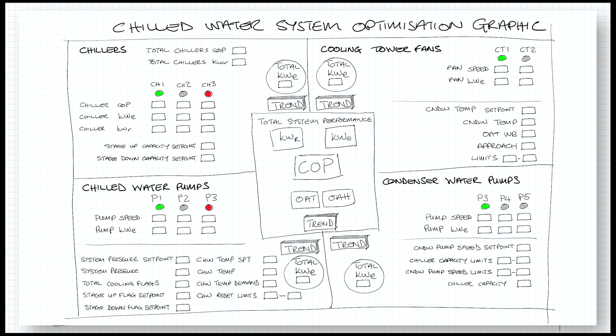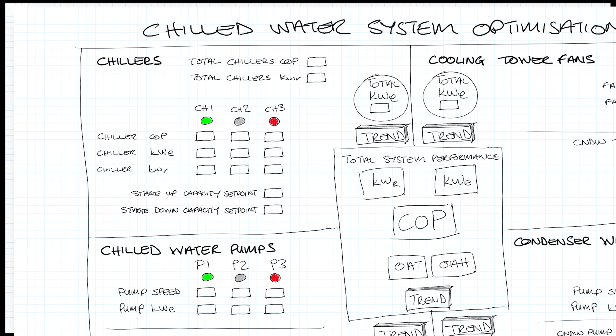If you're doing chilled water optimization on site, you have to have a page like this - if you don't, I'd propose you're not doing optimization properly. On the top left I have 'Chillers' with all the points associated with chiller staging: staging on capacity, and for each of the three individual chillers I have the COP, the electrical power consumption in kilowatts, and the kilowatts of cooling. A green dot means the chiller is running, gray means it's not running, red means it's in fault. I've also totalized the total chilled water COP for all three chillers and the total kilowatts of cooling.